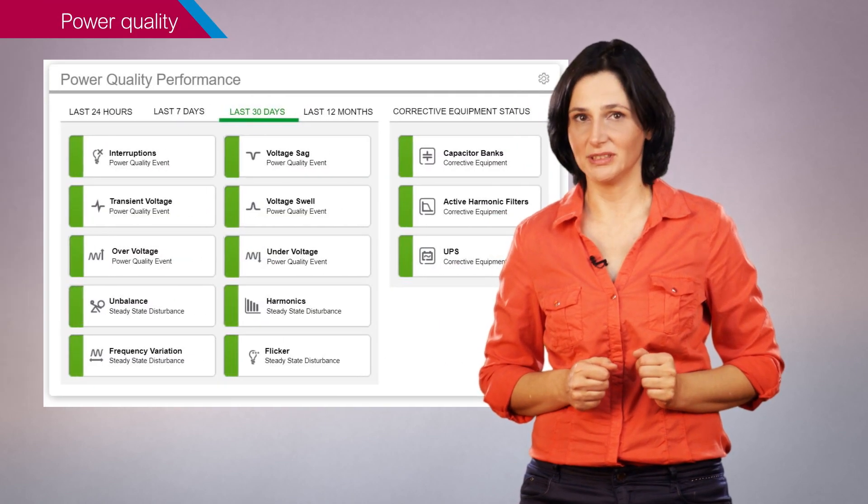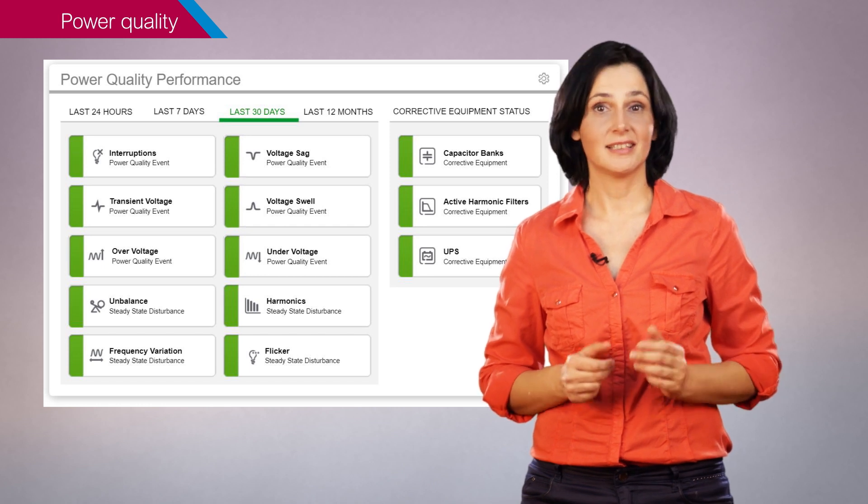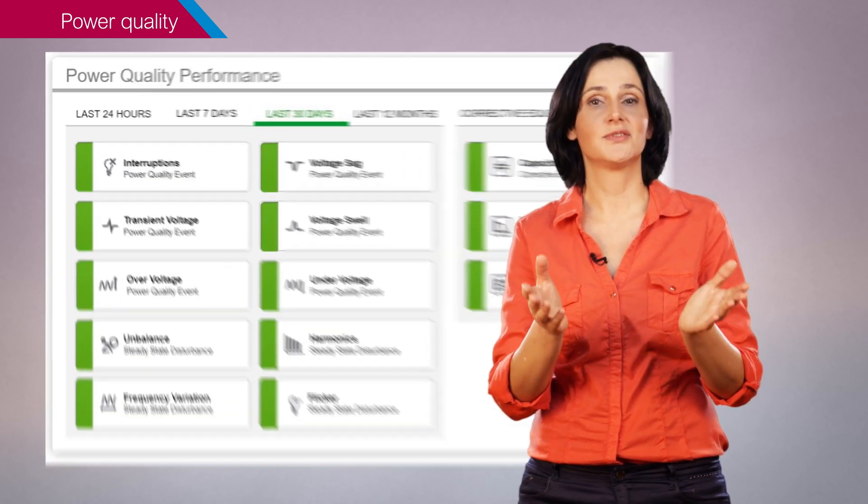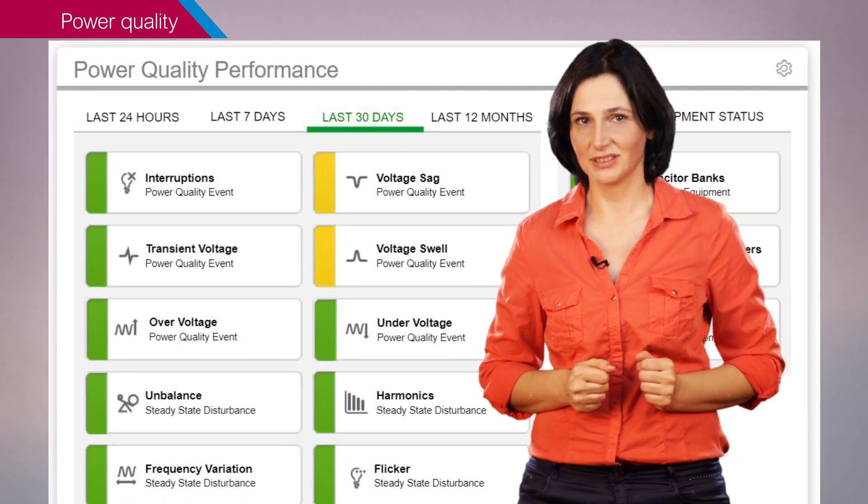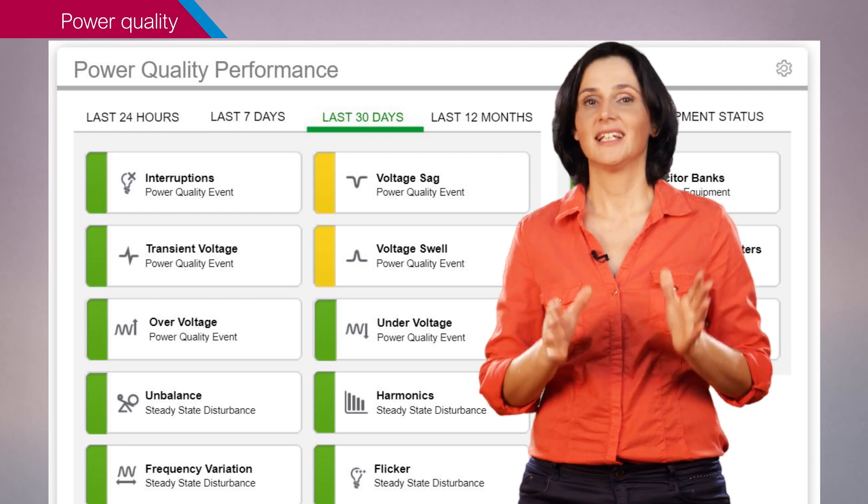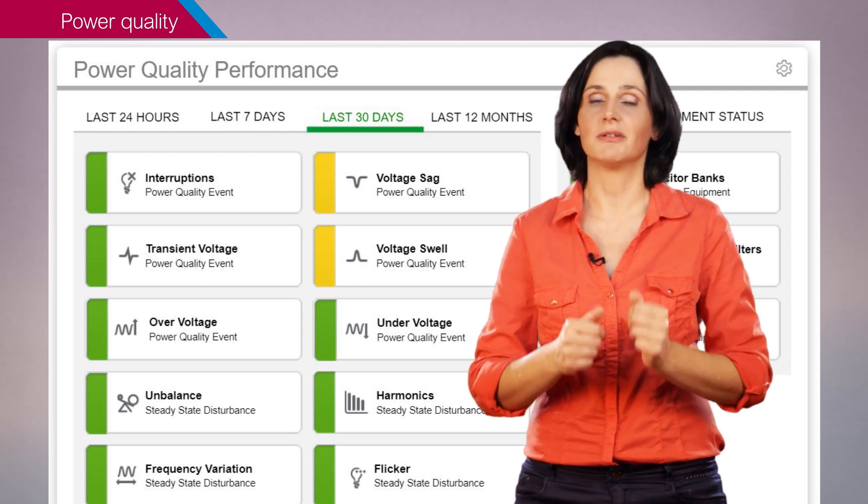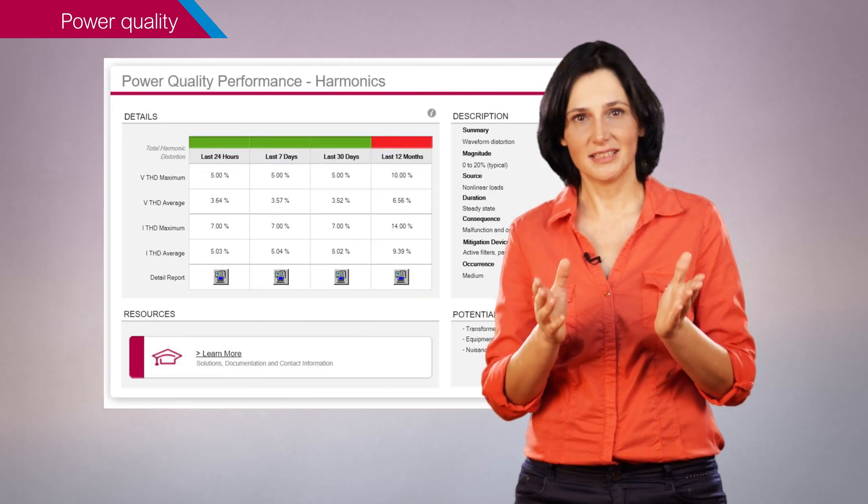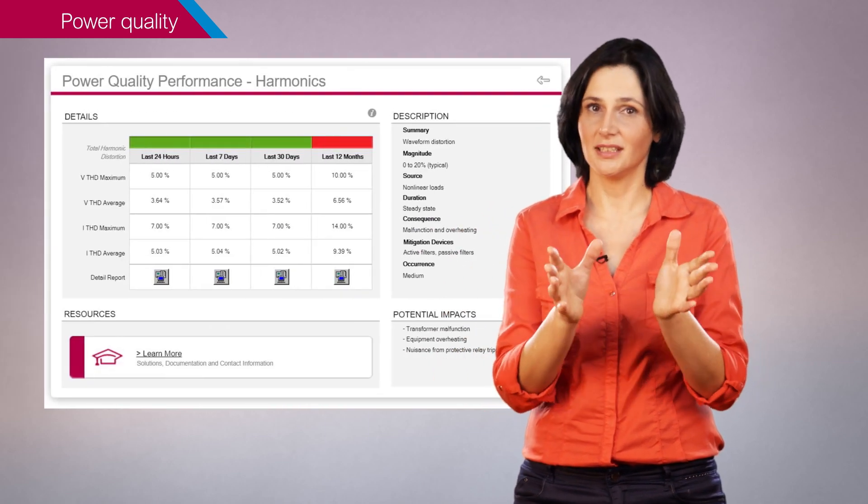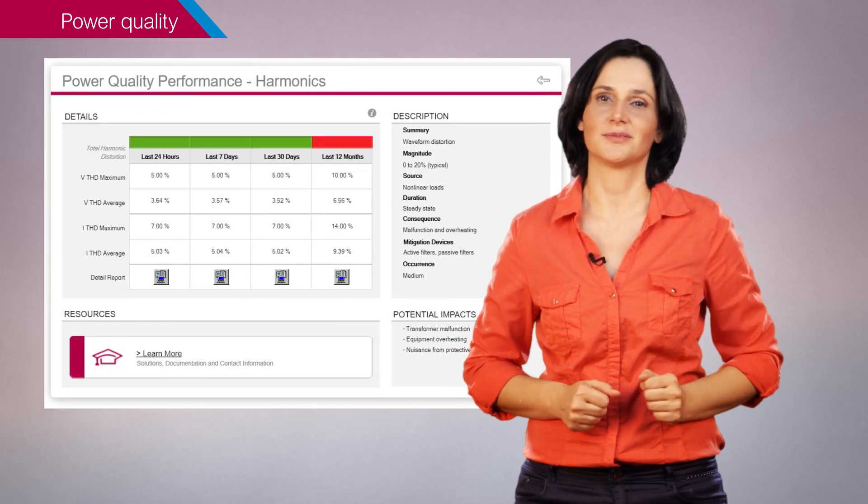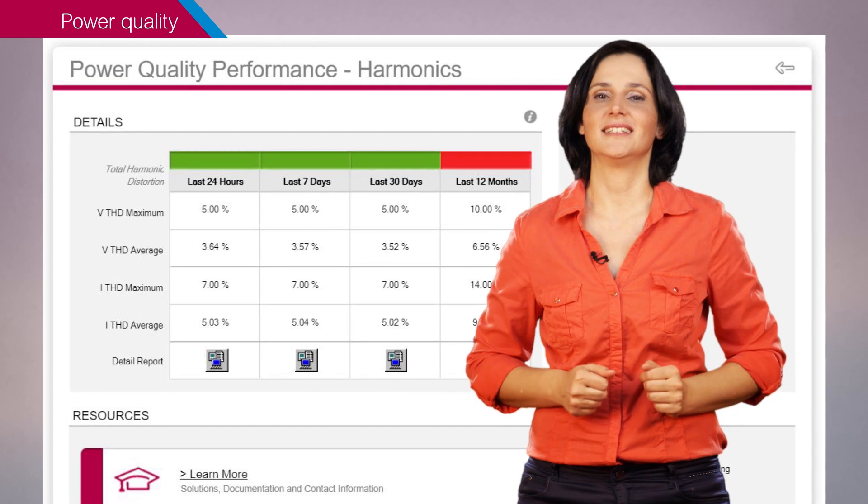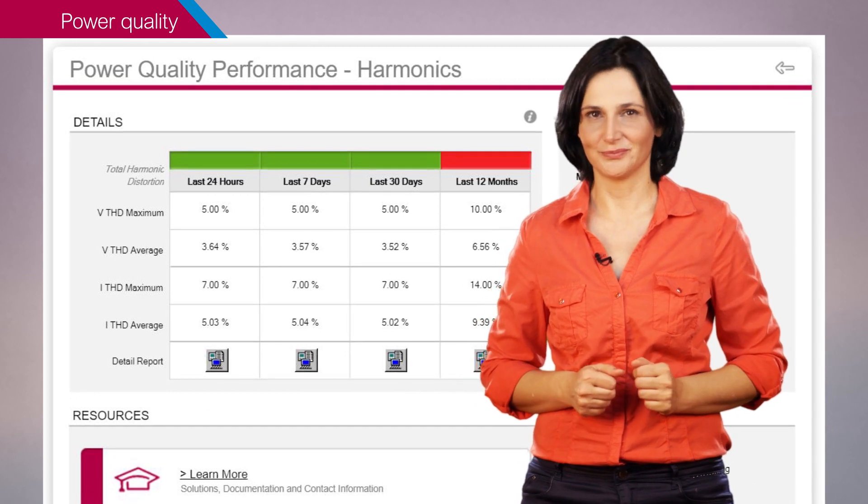Photovoltaic inverters can also have an impact on the power quality of the electrical installation and are sensitive to poor power quality themselves. The monitoring system should therefore measure power quality disturbances, especially for harmonics and unbalance. I explain that in another video.